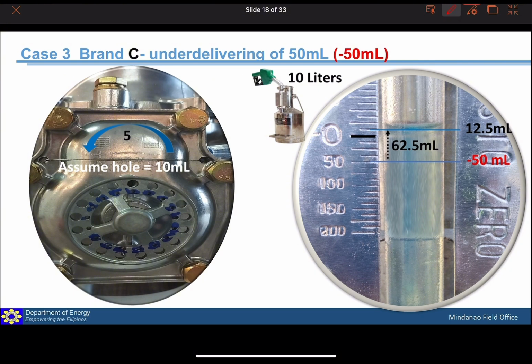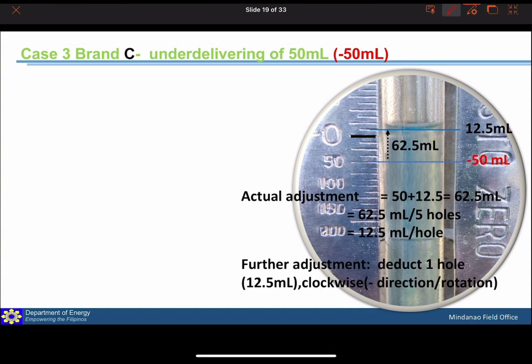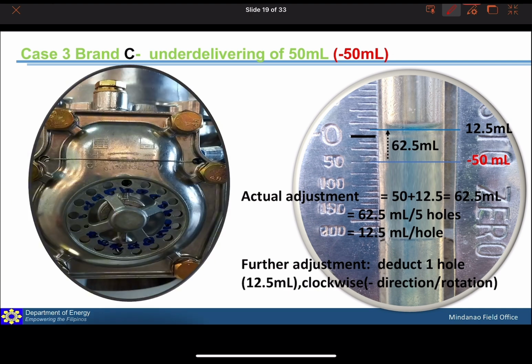So the difference or the adjustment is equal to 62.5 ml. Kasi 50 ml downwards plus the 12.5 ml. So actual adjustment is 50 ml plus 12.5 is equals to 62.5 ml. Then 62.5 ml divided by 5 holes, ang value per hole for this brand C is equal to 12.5 ml. For further adjustments, we need to deduct hole 12.5. So into clockwise direction naman. Isang hole.